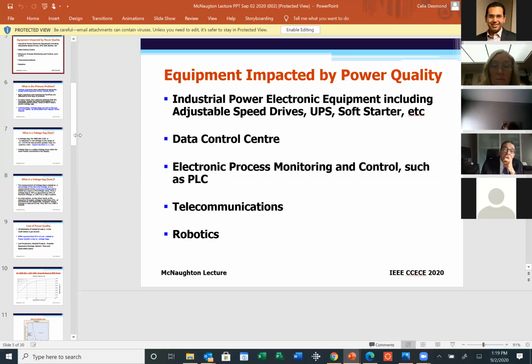Now, what is common to all these points is that they all use electronic switching devices, which means they might be using diodes, IGBTs, IGCTs, etc. The reason they use them is that some of their basic requirements, as the speaker before me talked about with DC and AC inverters, is that we convert AC to DC and DC to AC. This conversion requires these electronic devices, and these electronic devices are very, very sensitive to voltage fluctuation. Next slide, please.